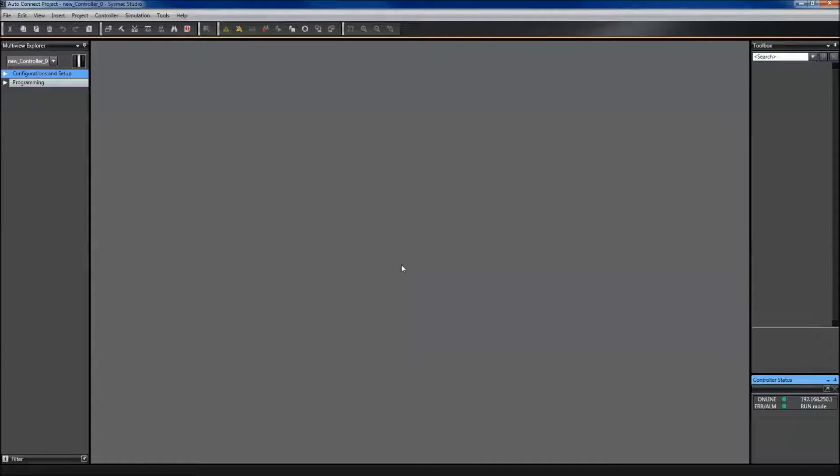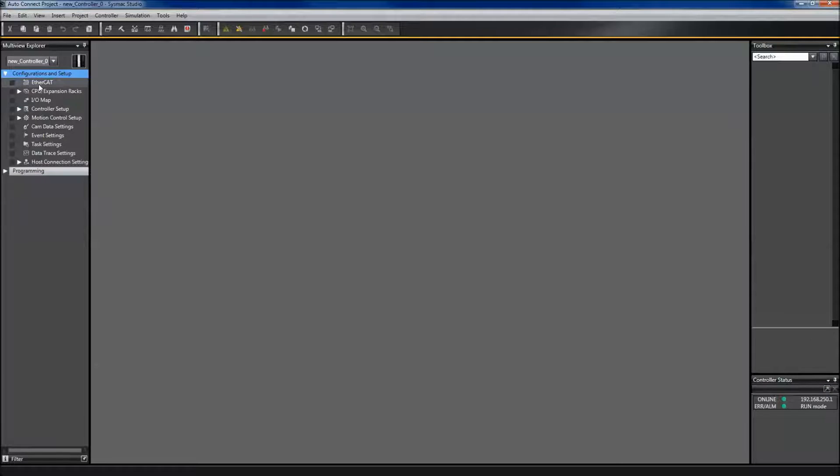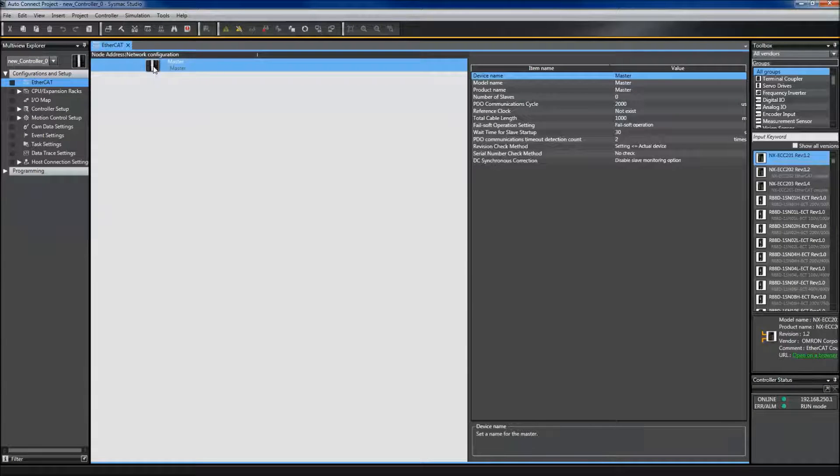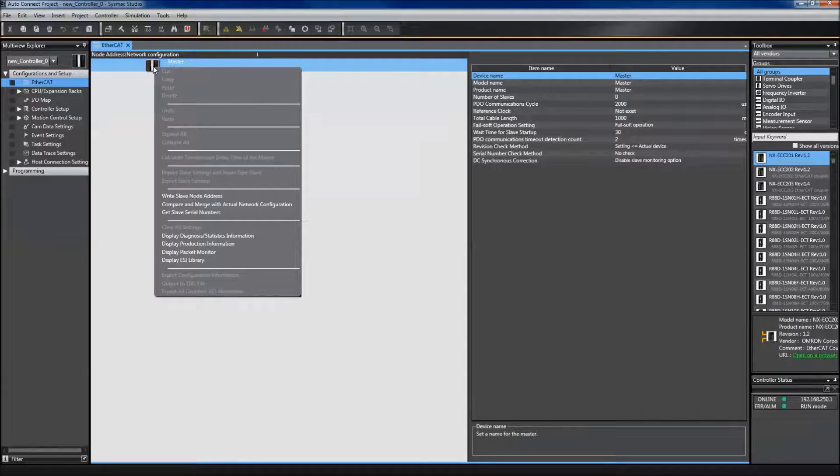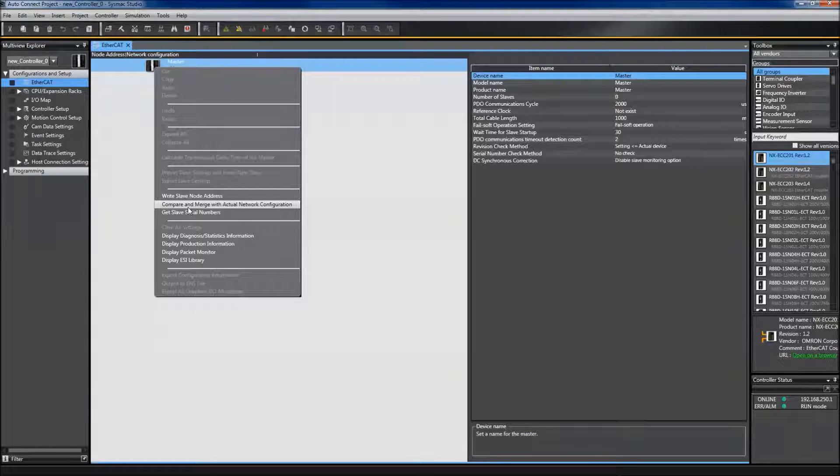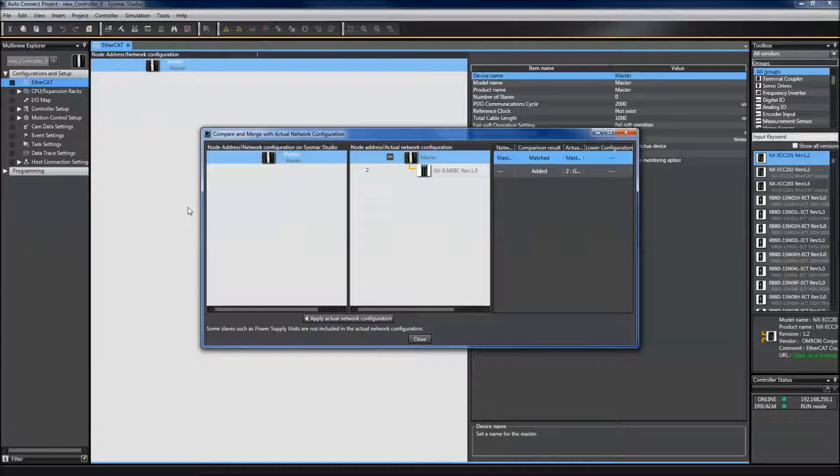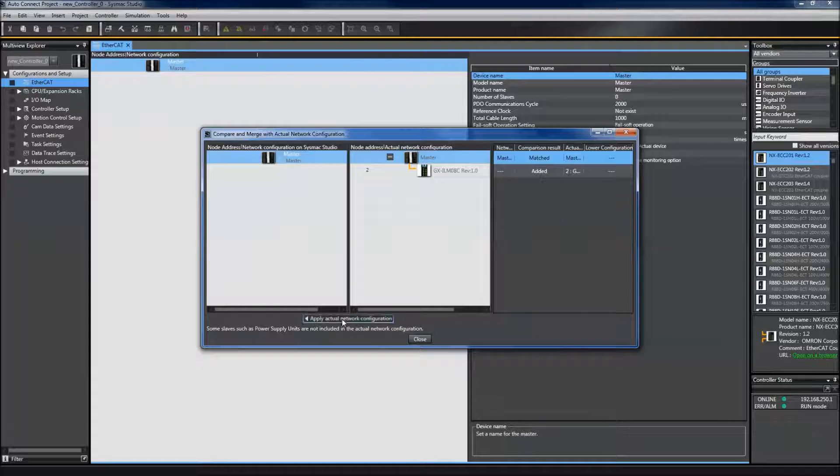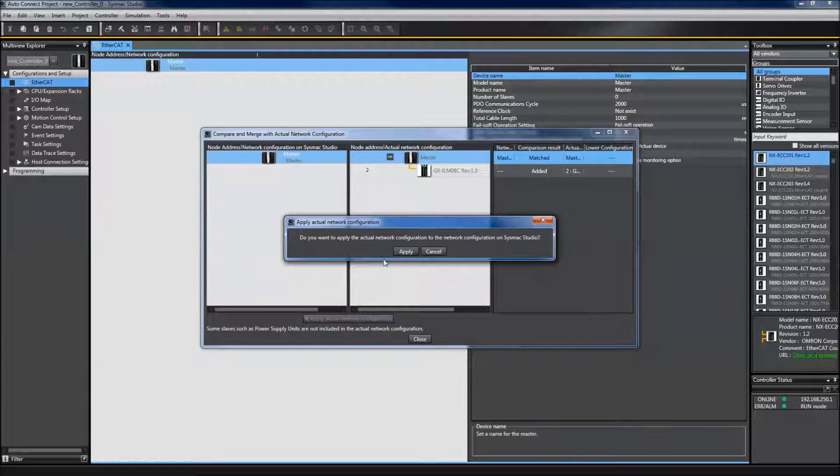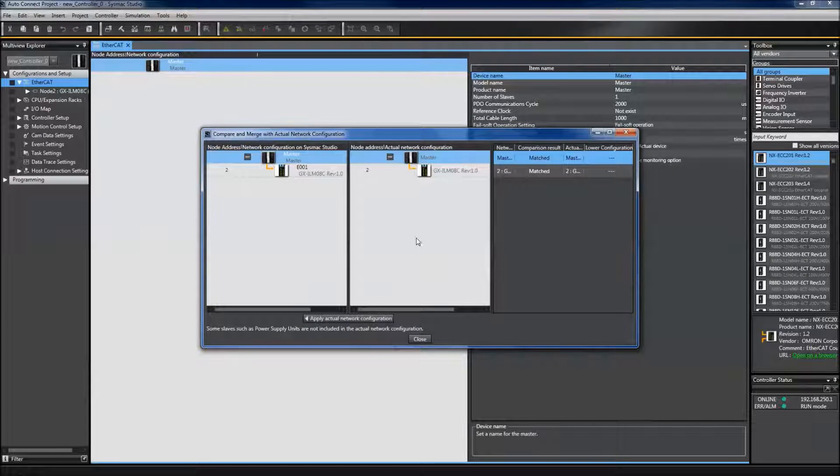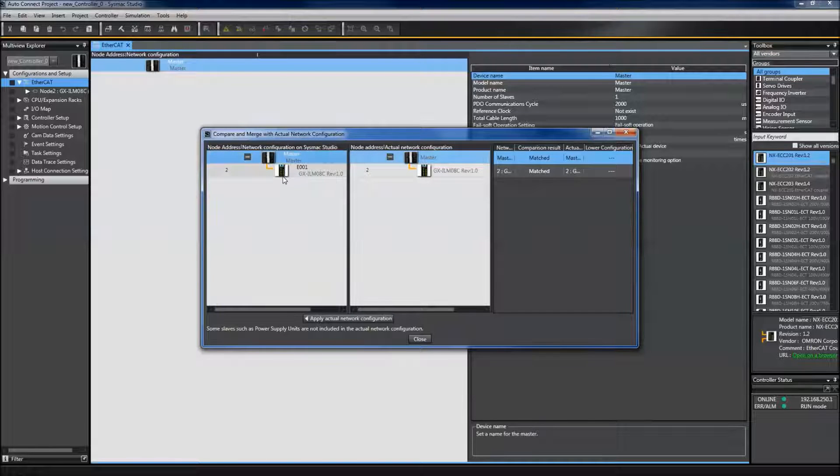Since my network is already set up, the first thing I need to do is go to my configurations and setup, select EtherCAT, right-click my master and compare and merge with the actual network configuration. This brings up the compare and merge window. I apply the actual network configuration and now my IO-Link EtherCAT slave is on the actual network.